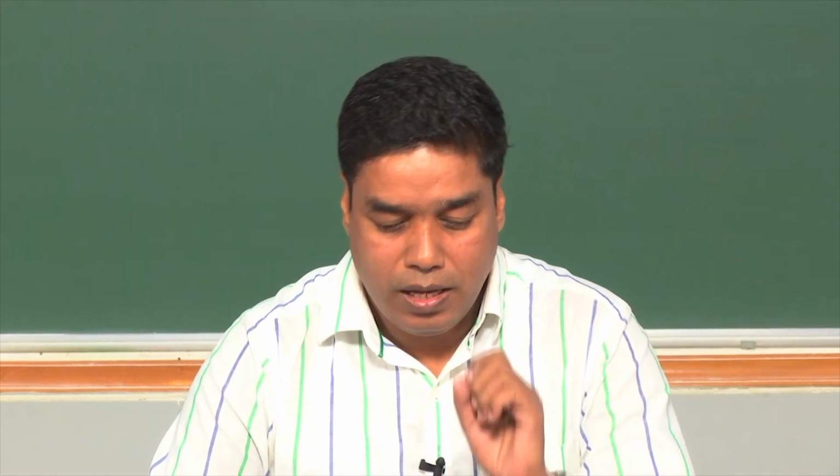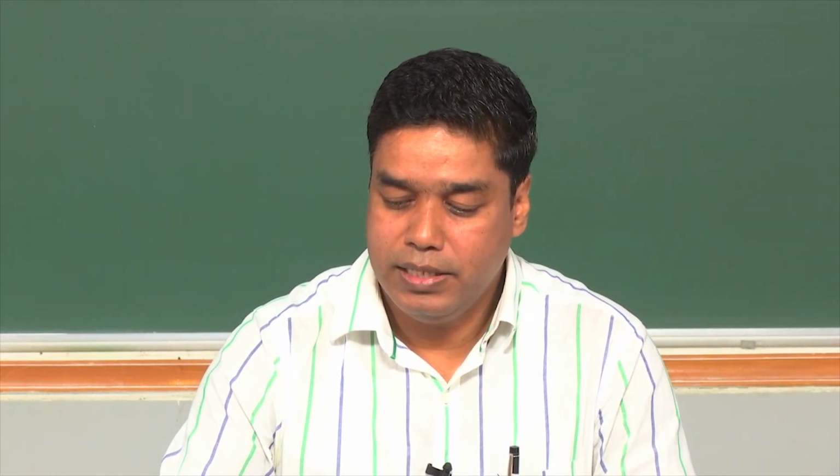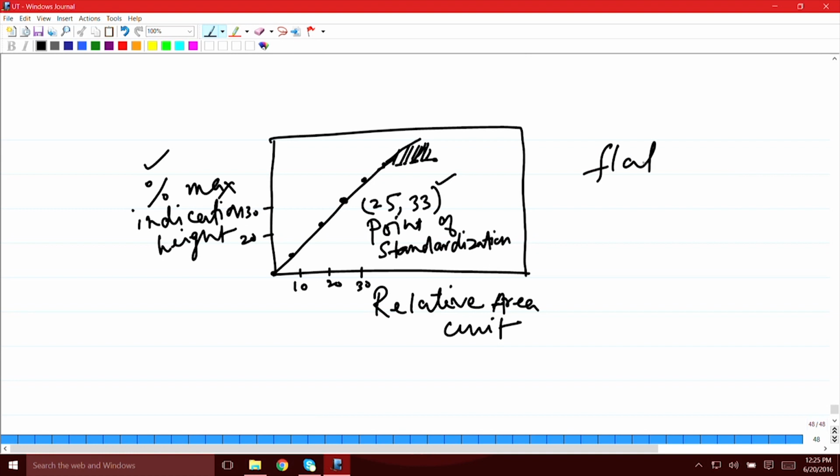Okay. But one thing you should remember, these flat bottom holes that we have introduced by precisely drilling, okay, are an ideal reflector.